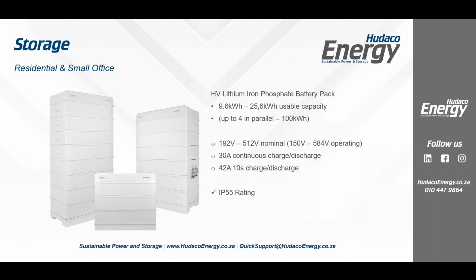Each one of these stacks is 3.2 kilowatt hours usable energy. So in other words, here we've got 3.2, 6.4, 9.6 kilowatt hours of usable energy in this battery. Okay, it's neat, it's compact. It replaces 20 kilowatt hours of lead acid plus all the cabling, plus the big DC box for your protection in between this and your inverter. And all you have is 4 cables. So your red, your black, your earth, and your comms cable that comes up in a single shaft in between and then into the bottom of your inverter. Right, so you need probably a 5 centimeter wide piece of trunking that runs up in between, and that's about it.